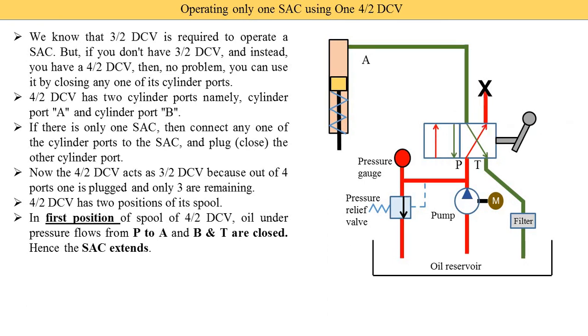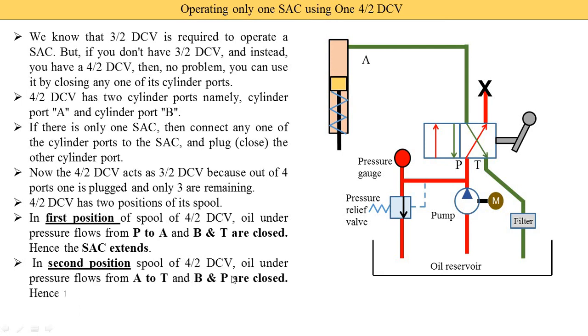This is the first position, and here is the second position of the directional control valve. In the second position of the spool of the 4/2 DCV, oil under pressure flows from A to T, and B and P are closed. P is connected with B, but you know that B is blocked, so pressurized oil goes to port B but is not supplied further to the hydraulic system — that is why it is written as closed.